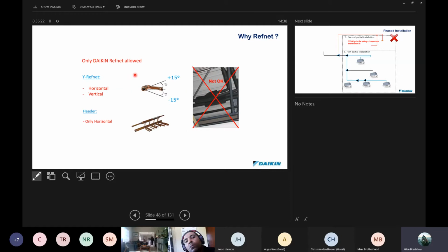Also remember, we spoke and you saw in the video that the Refnet must be horizontal. You can mount them vertical, but not turned up 90 degrees, when the whole joint is in the vertical plane. You can do that. And then headers, as I said, only in the horizontal plane. So here you see a Refnet that is mounted vertically. That is not acceptable. Your maximum angle is 15 degrees. And as far as I'm concerned, I don't know anybody who needs to mount something at 15 degrees. Aim for 100% horizontal with the Refnets.